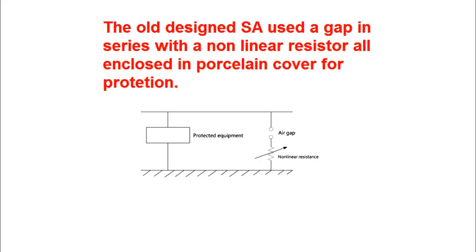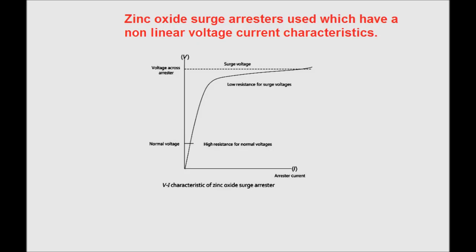The old designed surge arrester used a gap in series with a non-linear resistor, all enclosed in a porcelain cover for protection. The diagram shows the old type of surge arrester used in earlier days. The non-linear resistance provides high impedance during normal operating voltage, but when high voltage or any transient surge occurs, this non-linear resistance provides a low impedance path, and therefore sparkover occurs in the spark gap, thereby protecting the equipment from the surge.